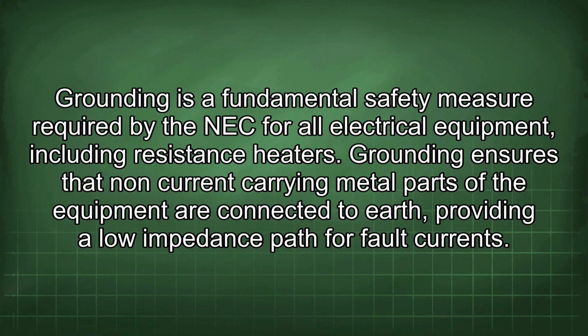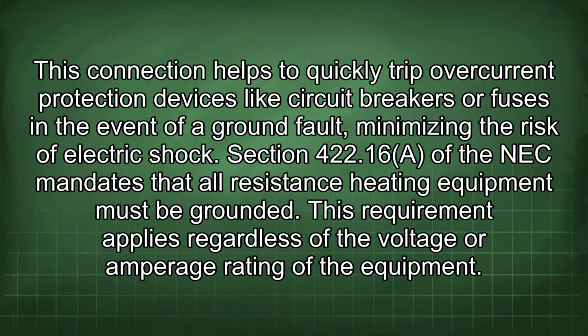Grounding is a fundamental safety measure required by the NEC for all electrical equipment, including resistance heaters. Grounding ensures that non-current carrying metal parts of the equipment are connected to earth, providing a low impedance path for fault currents. This connection helps to quickly trip overcurrent protection devices like circuit breakers or fuses in the event of a ground fault, minimizing the risk of electric shock.